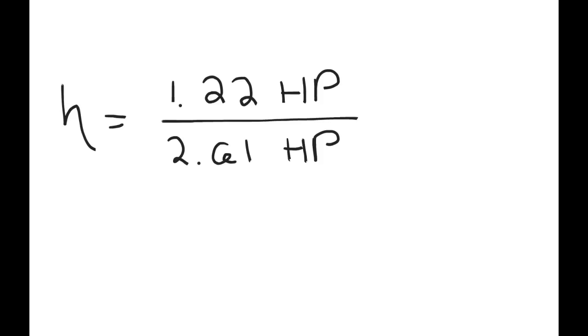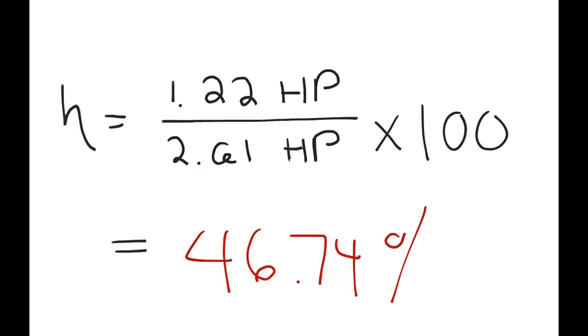Okay, so now that we have our system output and our system input both in horsepower, we can simply calculate the percentage of the efficiency of the total system. 1.22 over 2.61, multiply that by 100 to get it to a percentage decimal, and it comes out to an efficiency of 46.74%.